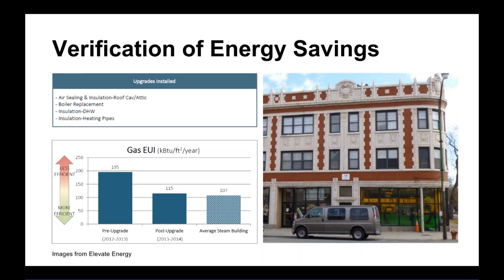One example building received upgrades including air sealing and insulation in the roof cavity, a boiler replacement to a high-efficiency model, insulation on the domestic hot water system, and pipe insulation on heating pipes. The pre-upgrade EUI was pretty high for a steam building, but after completing all those upgrades, they were able to cut their energy use by about 40%. There are also non-energy benefits: increased comfort for tenants and decreased maintenance costs since they no longer have super old equipment.